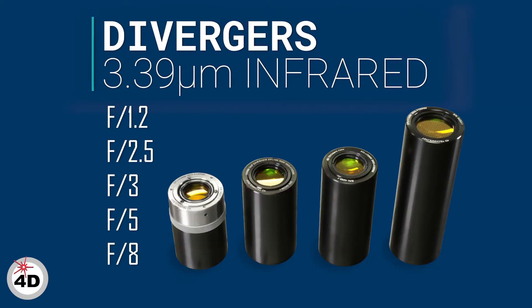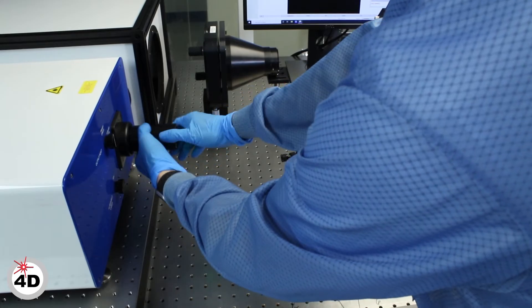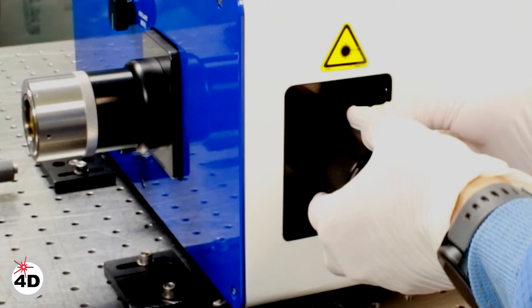The PhaseCam MWIR can be equipped with a range of IR diverging optics for measuring concave optical shape and transmitted wavefront error through the main output aperture on the front. Diverging optics are smaller, less expensive, easier to work with, and create fewer measurement artifacts than the transmission spheres used with Fizeau systems.